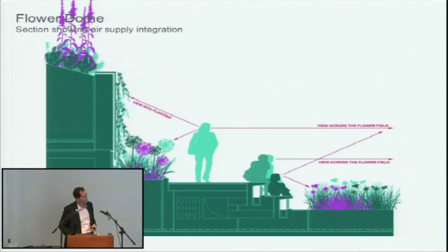And we can just start to see how, in some of the simple steps, you get a very light grill work that has very low velocity air coming out of it, and actually you can't tell that there's air coming out of it, to the extent that a few months ago when I was on site, one of the air handling units was being taken offline, and to check which grill had air coming through and which didn't, I had to get a cigarette lighter and hold it up to a number of different grills until I found the one where the flame didn't flicker.